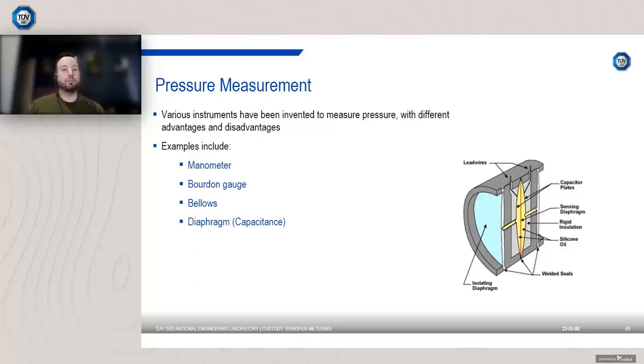When it comes to pressure measurement, various instruments have been invented to measure pressure with different advantages and disadvantages. I'm not going to go through every single type of pressure measurement device. A really common type of device is a capacitance diaphragm sensor. This is where you've got a sensing diaphragm between two capacitor plates, and when you apply a pressure to the diaphragm, it deflects in relation to that pressure. By measuring the change in electrical capacitance, you can relate that back to the applied pressure. Depending on what you're measuring, if it's gauge pressure, you might have one side where you're applying your pressure, and the other side is open to the atmosphere. If it's an absolute pressure transmitter, one side might have a vacuum and the other side is your applied pressure.